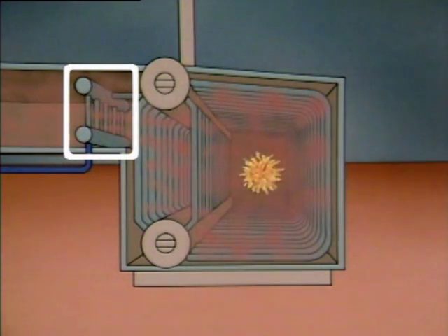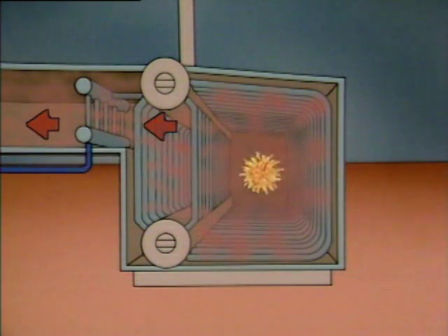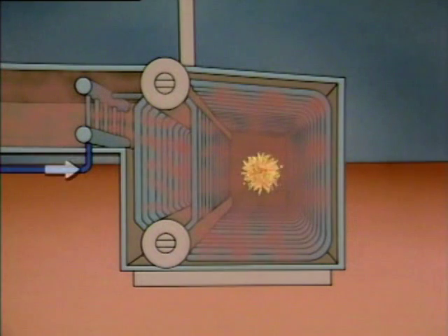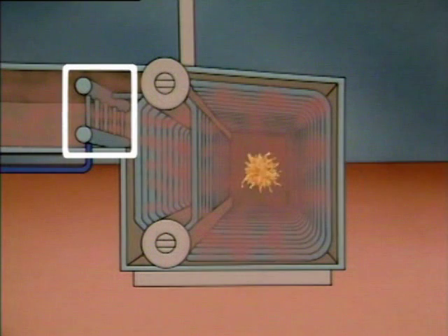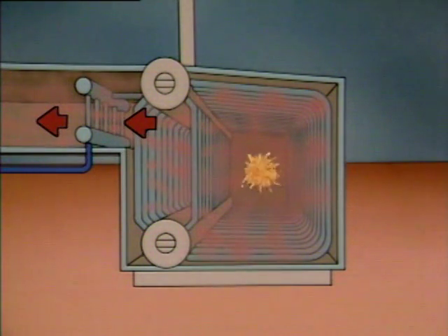An economizer is basically a series of water tubes located in the flow path of the combustion gases. Feedwater is routed through the tubes on its way to the steam drum. The water is heated by the hot combustion gases flowing past the tubes. The economizer improves boiler efficiency by making use of heat in the combustion gases that would otherwise be wasted.